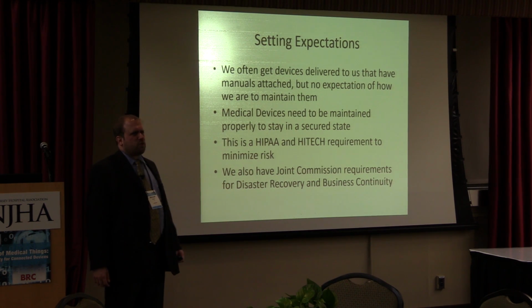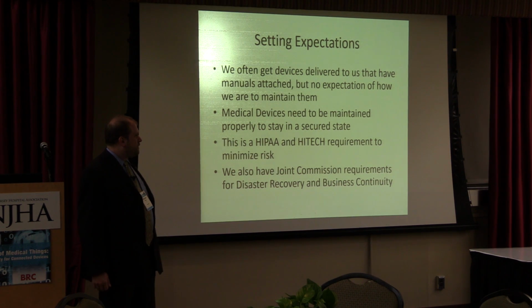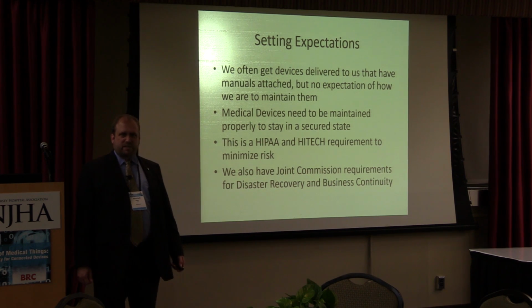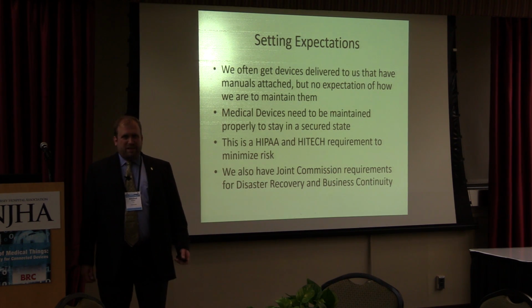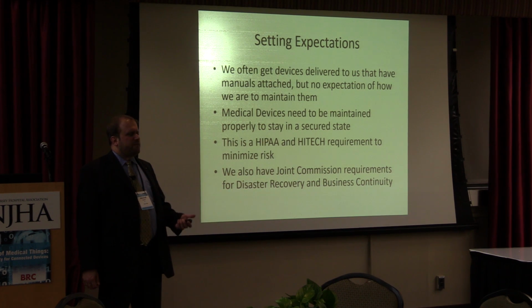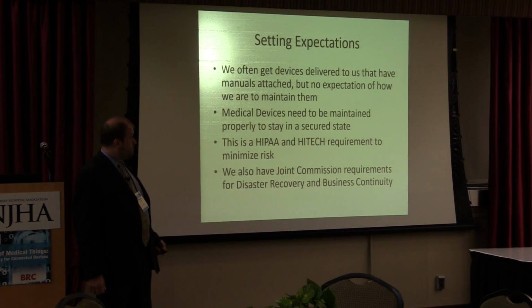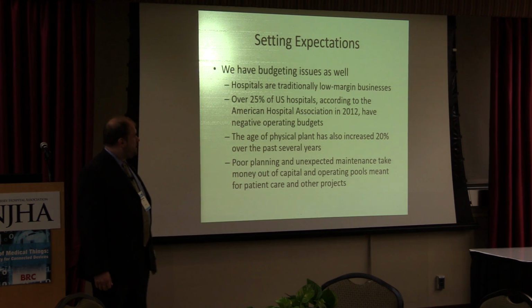And we also have Joint Commission requirements. I'm surprised I didn't hear that. When it comes to hospitals, we have Joint Commission requirements for disaster recovery and business continuity. And what happens when you don't have a network? So we have to plan for everything. And sometimes that includes manually operating a device, knowing how the device operates, so that you can write how to use this device if the network's not there, so people know how to use it to take care of a patient. And it also comes down to budgeting issues.